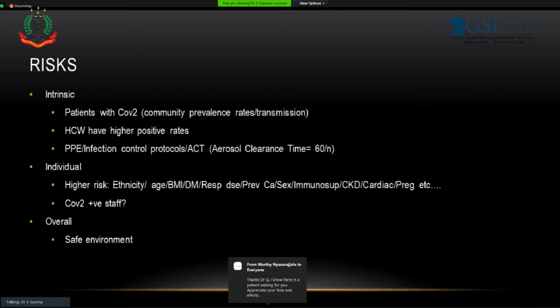For instance, I've got a knee replacement on the table right now as I speak to you. Once the knee replacement is done, this theater has about 20 changes of air per hour. So the aerosol clearance time is 60 divided by the number of room air changes - that's 60 divided by 20, which is 3 minutes to clear about two-thirds of the viral load. In real terms, you need to wait for about 5 or 6 of those changes before you can go on with the next patient. So in this theater, I'll be standing down for about 25 minutes between cases.